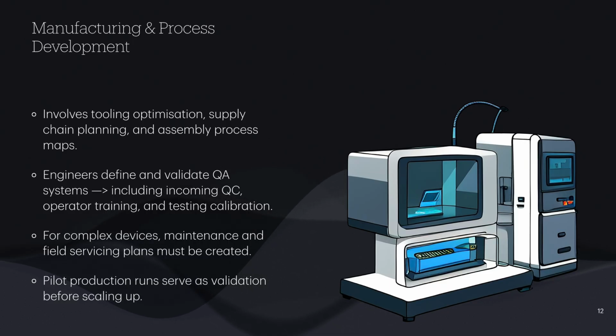But companies find creative workarounds, such as using manual assembly lines to reduce capital costs, training operators directly from nearby communities, and establishing pilot runs. These are small batches between 100 and 500 units for final process tuning. Sanapi, for instance, used a manual packaging process that still met ISO 11607 sterility standards by proving integrity through testing rather than automation. This phase is where your design becomes a product, reliably, safely, and affordably.